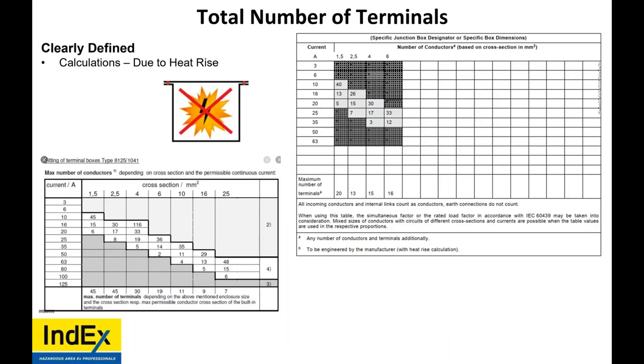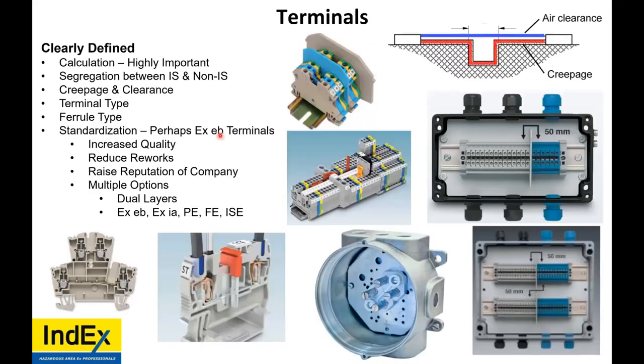Now, when selecting the total number of terminals within your box, as per the standard, it's clearly defined based on the overall current, the size of the conductors, the size of the terminal's acceptance, and how many can be selected. So the standard tells you, and also the manufacturer tells you. Generally, the manufacturer does all the calculations. So you can order an Ex e box, but they're going to ask you what power usage you are going to have in that box. Now, to go back to terminals, there's the difference between screwed and spring types.